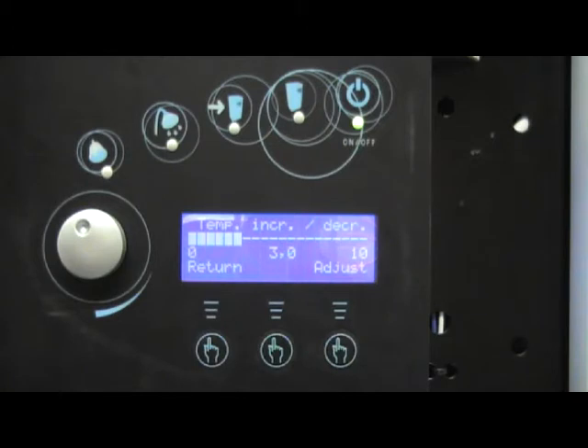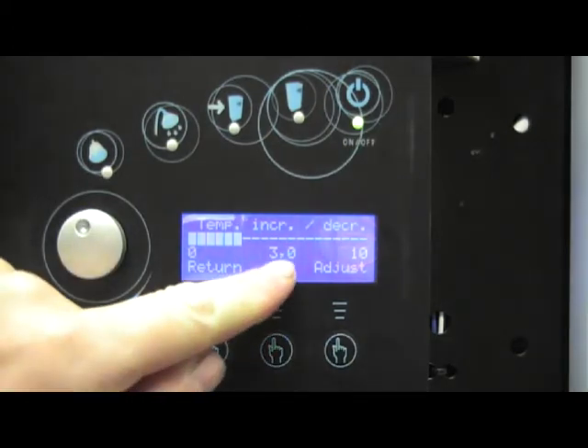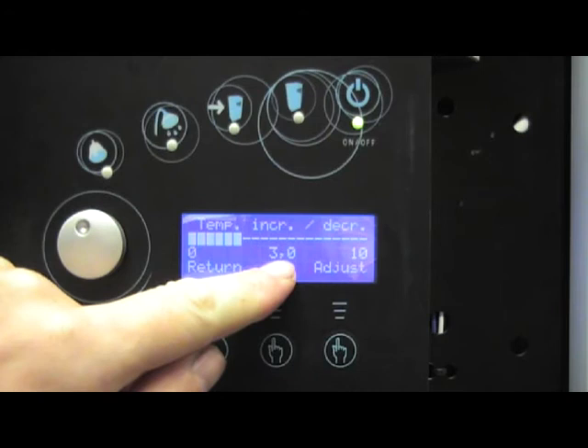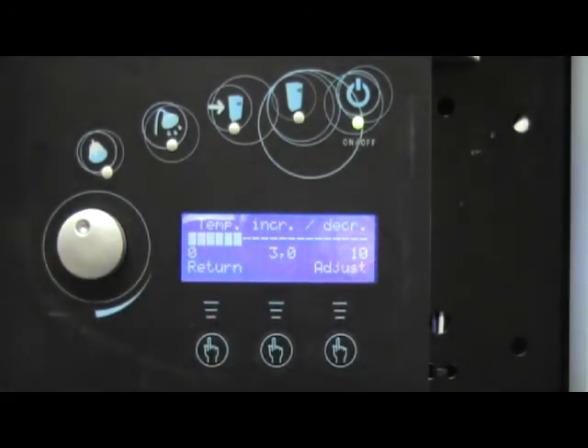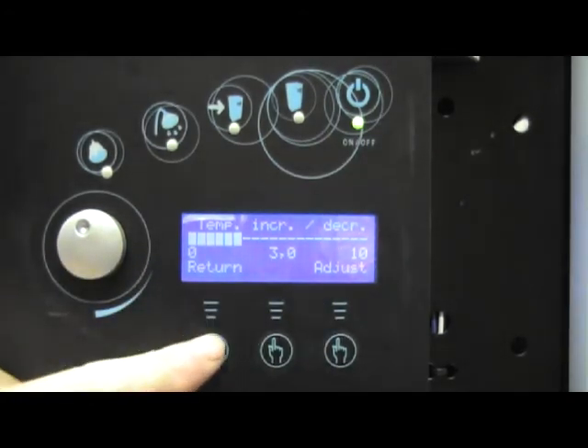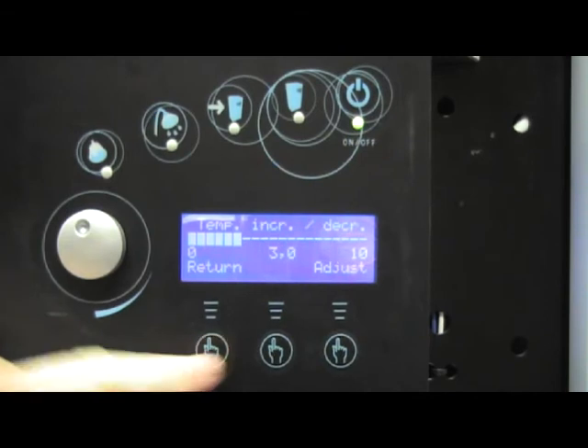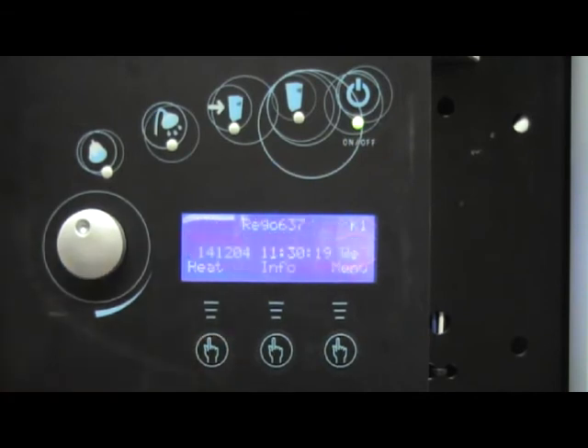If you have a radiator only system, you would be setting that figure there to about 4 to 5. When we are happy with our setting, we can press return and it goes back to the normal display.